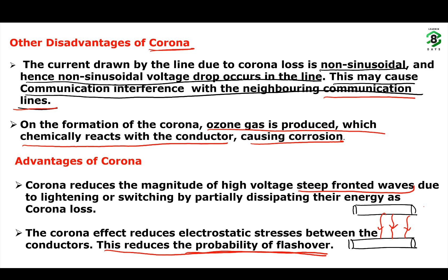So when a conductor is in the state of corona, if some high voltage transient occurs because of some switching operation or lightning, the steepness of this transient wave is reduced by dissipating its energy in the form of corona loss. The second one is corona effect reduces electrostatic stresses between the conductors, thus reduces the possibility of flashover. So once corona occurs, the probability of short circuit or flashover between the conductors is reduced. Why? Because it reduces the electrostatic stresses between the conductors.